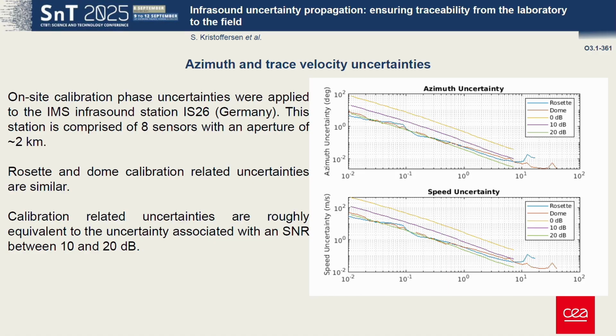And so we can see, for reference here, the blue curve shows the uncertainty response for rosette calibration. The red is a dome. And then additionally, I have the theoretical uncertainties associated with 0 dB, 10 dB, and 20 dB in yellow, purple, and green. The important takeaway here is that when we look at the dome and the rosette, we're seeing similar uncertainties related to the calibration. So that's a good sign that we're not degrading our results substantially by using a dome versus a rosette.